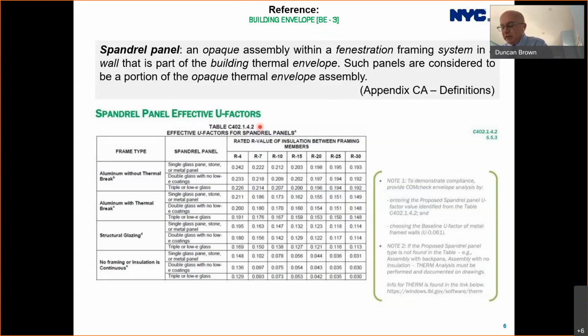The ASHRAE Appendix CA has the equivalent table 5.5.3. So you have to select either the frame type between aluminum without a thermal break, aluminum with a thermal break, structural glazing, or continuous glazing. Once you've done that, you then go on to pick the panel material, whether it's stone, metal panel, or a form of glass. Based on that, you select the R value of the insulation that you have between the framing members, and that would be the value that you enter into ComCheck.